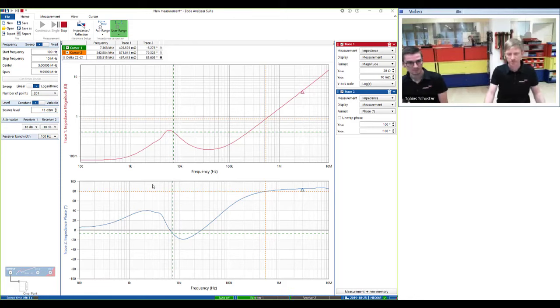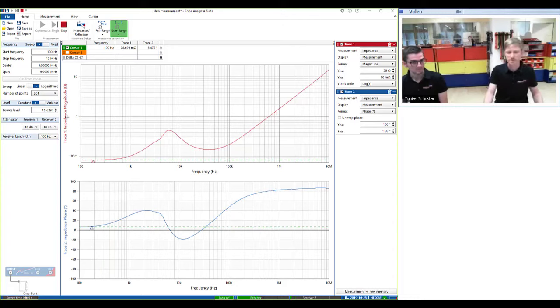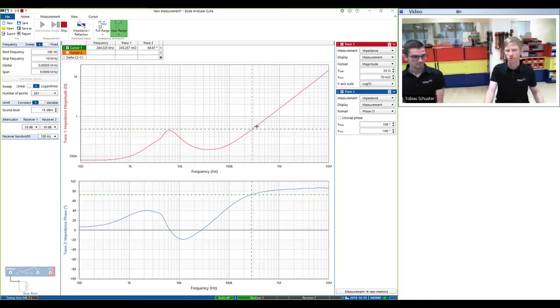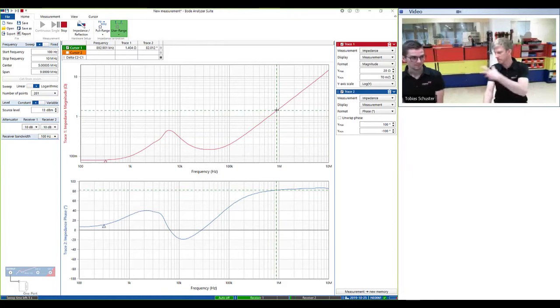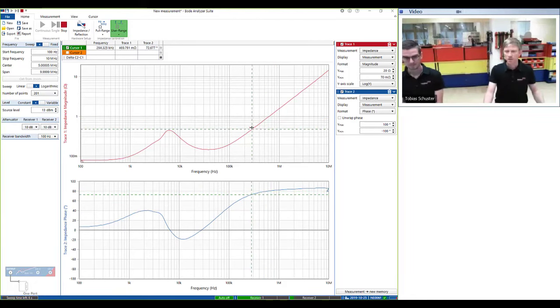So first let's have a look at the curve. We see at 100 Hertz there is a very low output impedance of, let's use the cursor and drag the cursor here, it's around 80 milliohms of output resistance. Then there is a peak in the output impedance at around 6 kilohertz. That's from the control loop. Then we see the impedance falling again, and in the end rising from parasitic inductance. And as I said before, the parasitic inductance of course will be too high, because we are also measuring the parasitic inductance of our connection leads.